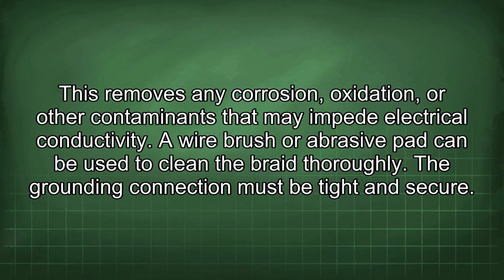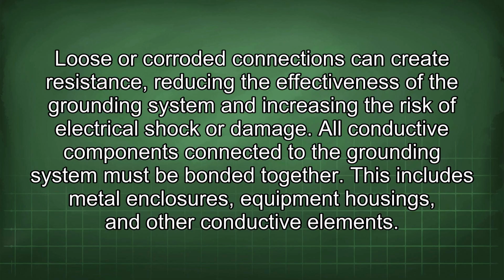A wire brush or abrasive pad can be used to clean the braid thoroughly. The grounding connection must be tight and secure. Loose or corroded connections can create resistance, reducing the effectiveness of the grounding system and increasing the risk of electrical shock or damage. All conductive components connected to the grounding system must be bonded together.